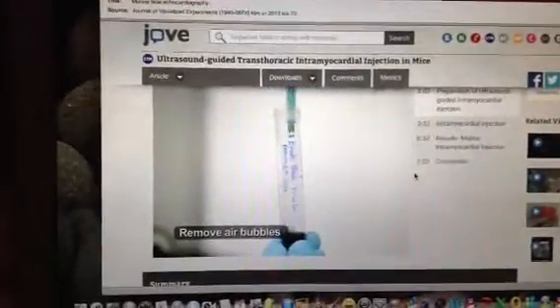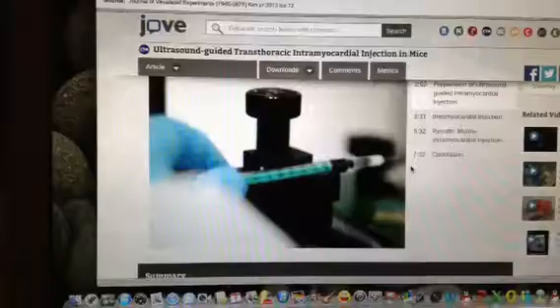Remove the syringe that was used for alignment from the syringe clamp and carefully discard it. Load the new needle and syringe with the injectate to the final target volume, allowing for dead space in the syringe tip. Place the syringe into the syringe clamp without adjusting its x-axis alignment and use the injection control to fully retract the syringe.